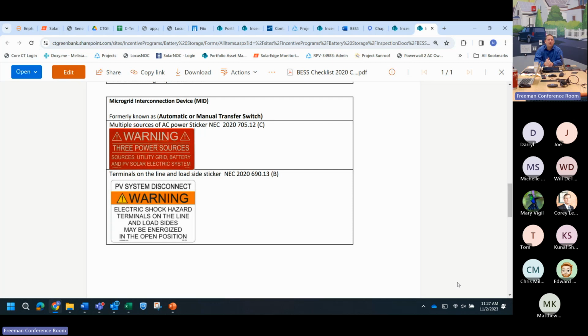Almost always, because this is where your main bus is, your AC bus, your backup bus if you will, that will always have the potential for line power on the box, even if they shut off the main breaker, or even if they shut off the main input from the street. So the sticker warning, terminals on the line and load sides may be energized in the open position, that is a valid warning.